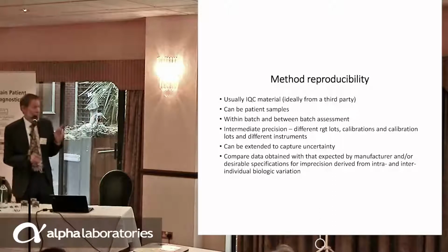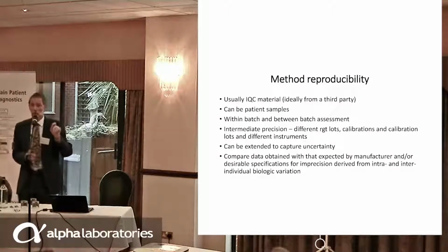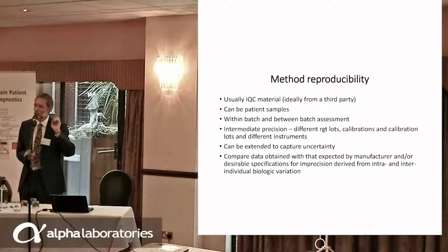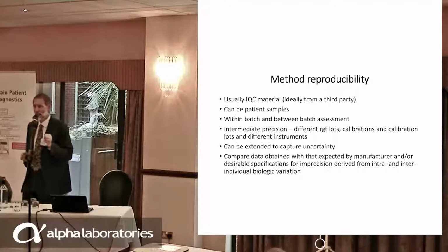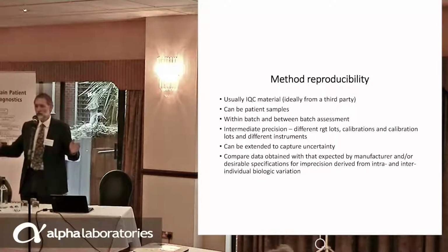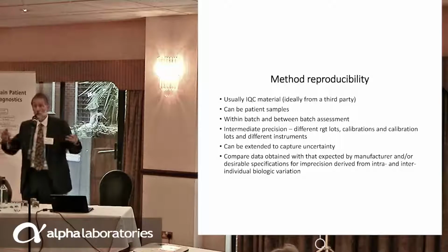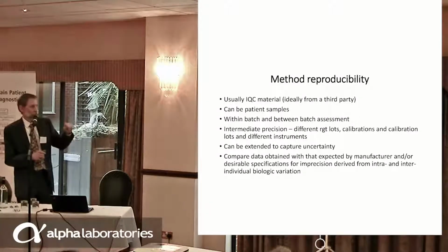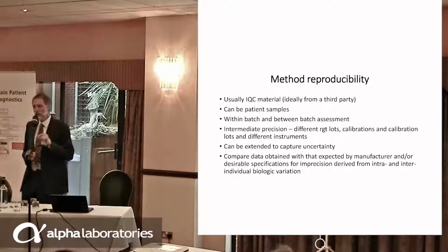So I think the important thing is that at some time in the future, you update perhaps with an appendix to your report to say, okay, now I've looked at the intermediate precision, and whilst it was fantastic over a 2-week period when I put the analyzer in, now, over 6 months, I know that all these variable factors have contributed to a total imprecision, a total uncertainty of Y%, for example.